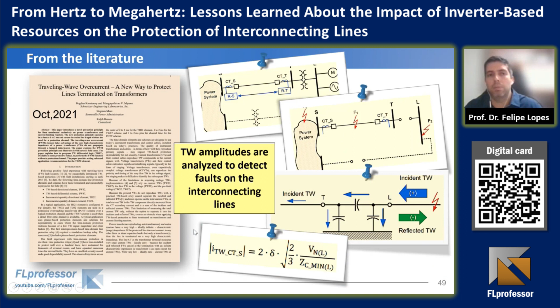So these additional oscillations are observed, and they are a point of attention, and they occur basically due to the termination influence, which is a transformer. So a summary of the conclusion in this paper regarding the differential traveling wave based elements: it correctly restrained for the evaluated external faults. The case of low stray capacitances led the scheme to lose sensitivity, which is expected because the amplitude of the induced traveling wave is reduced, so the security conditions will block the function. The distortions in the measured traveling waves are a point of attention, as I mentioned earlier, especially for external faults on the grid side. But the conditions used guaranteed the security, especially regarding the amplitude of the waves.